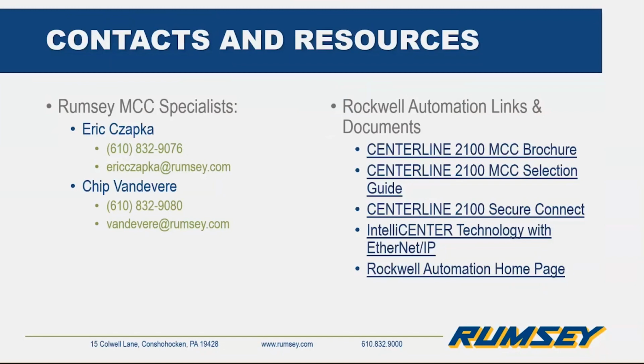I wanted to point out that the functional safety option Eric was discussing is unique to Rockwell. You're going to be able to utilize the motor control output of your MCC and incorporate it into your risk assessment process. So you could realistically have an e-stop set up on your MCC, your safety relay, and your motor control output, all documented with verification plans, all documented for you as part of the MCC shipment. So that's of real value.